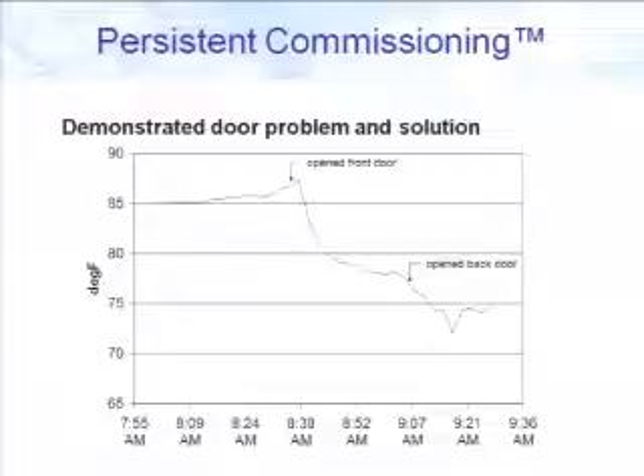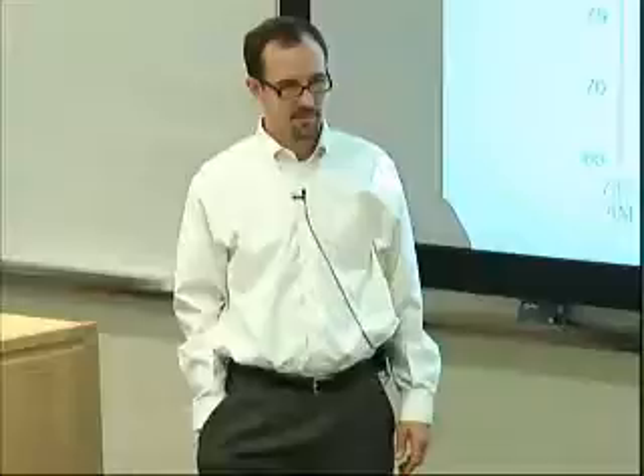This is kind of an interesting insight - I'm not sure if you guys have run into this, but it's always fascinating. A lot of racks have doors on them, right? They're 95% perforated, and most people say that's fine, and there are studies saying it doesn't affect airflow. But we've seen, in one instance, over a 10-degree drop just from opening the front and back doors.